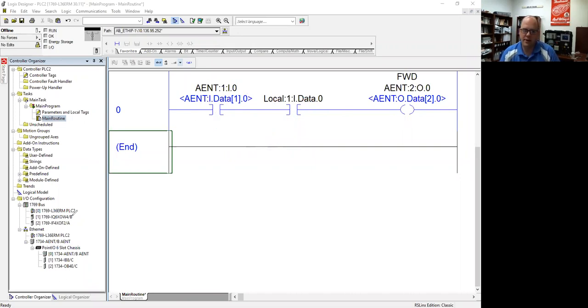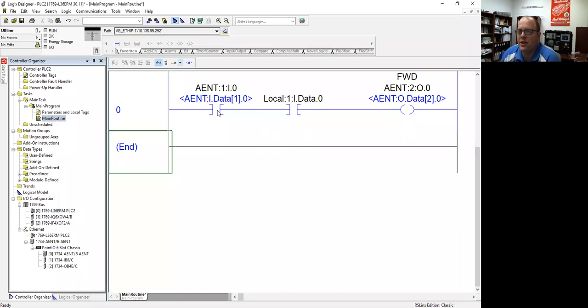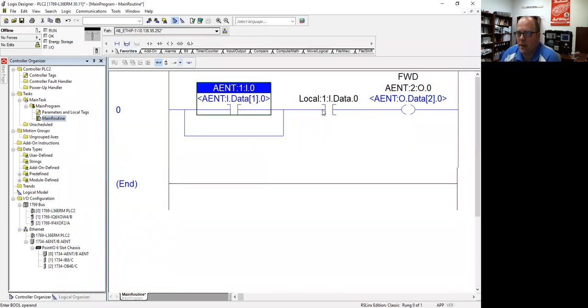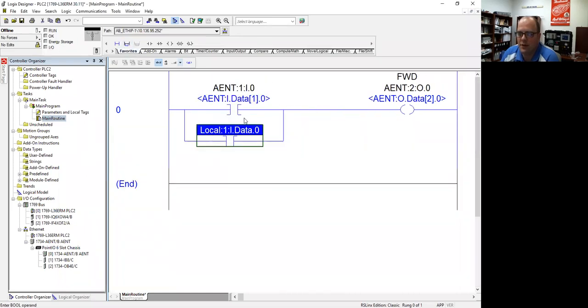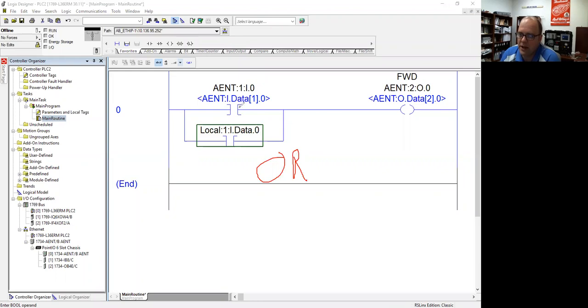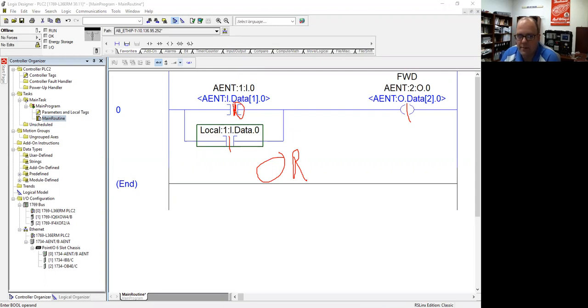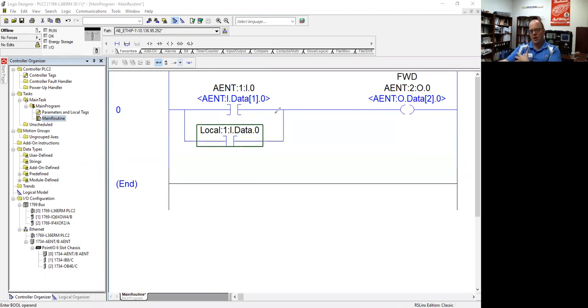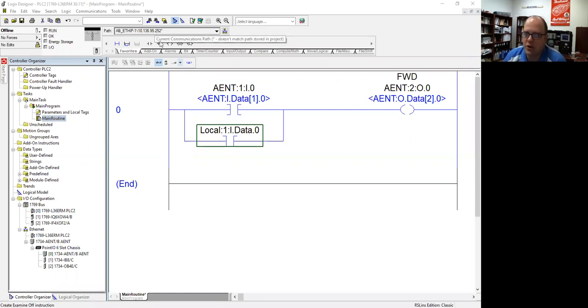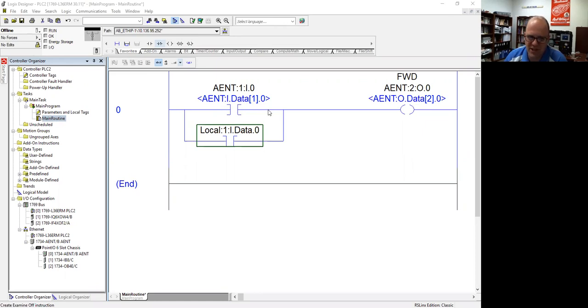And so, now, if I do it like this, this is considered OR logic. Because, remember, this is what we call parallel back in basic electricity, but this is OR logic, meaning if this is a 1 or if this is a 1, make this a 1. So if this is a 0 or off, this would be on. If this was a 0 and this was a 1, so if this was a 0, this would be on. So this is considered OR logic. So if I have multiple inputs that I want to turn on an output, I need to create a branch because this will allow those different paths. Now I can also go in, and I'm not going to talk about NANDs and NORs, those, let's just, because those can get a little confusing.